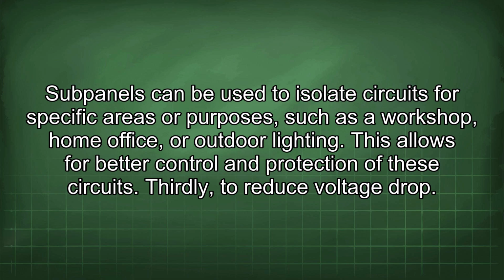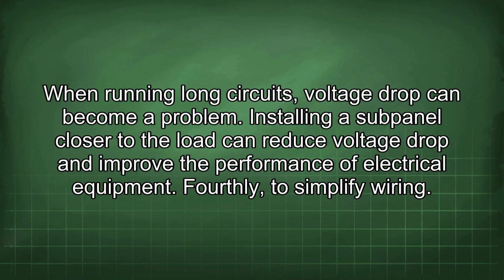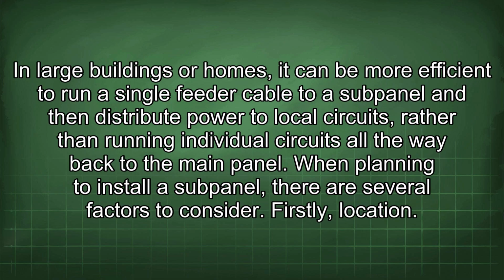Thirdly, to reduce voltage drop. When running long circuits, voltage drop can become a problem. Installing a subpanel closer to the load can reduce voltage drop and improve the performance of electrical equipment. Fourthly, to simplify wiring. In large buildings or homes, it can be more efficient to run a single feeder cable to a subpanel and then distribute power to local circuits, rather than running individual circuits all the way back to the main panel. When planning to install a subpanel, there are several factors to consider.